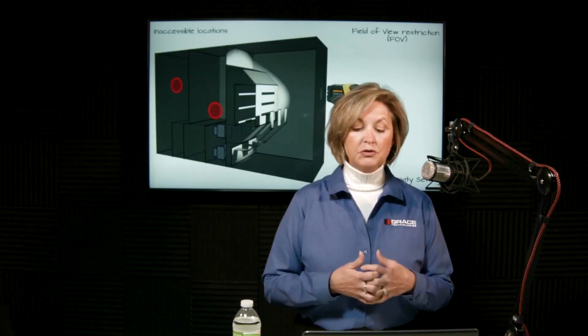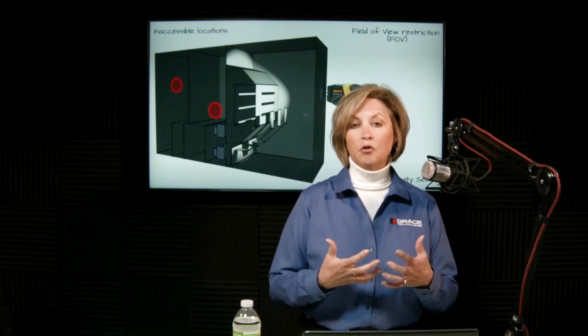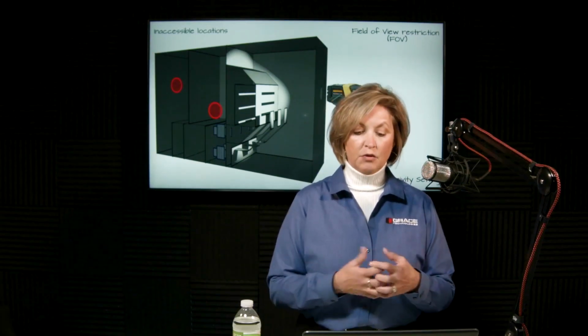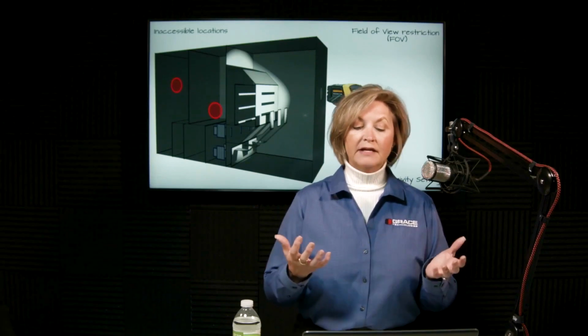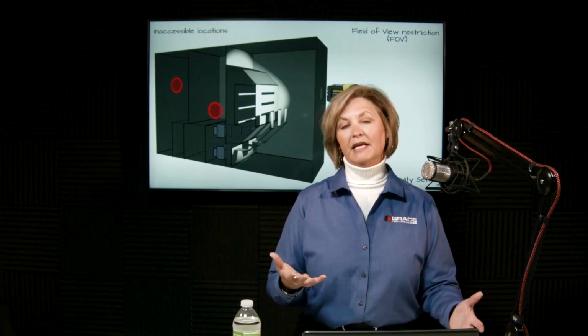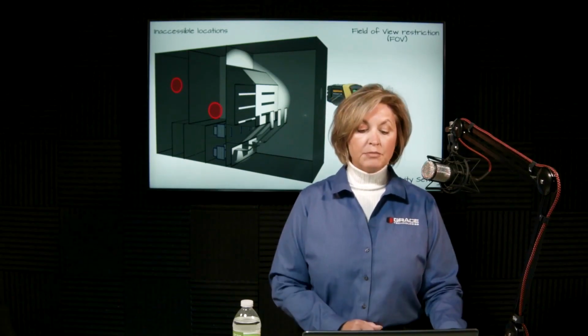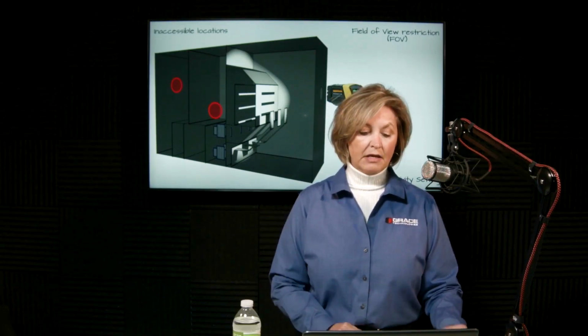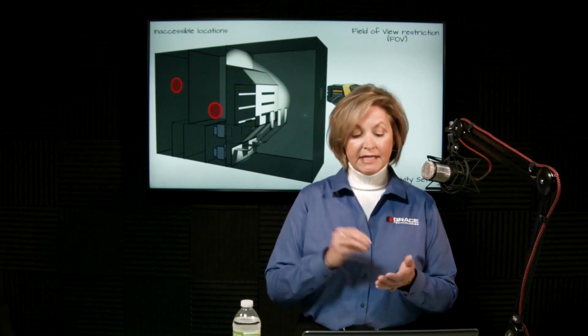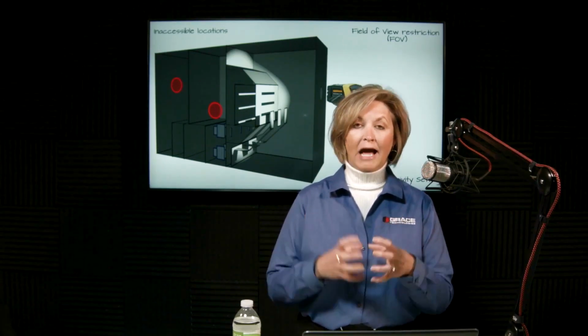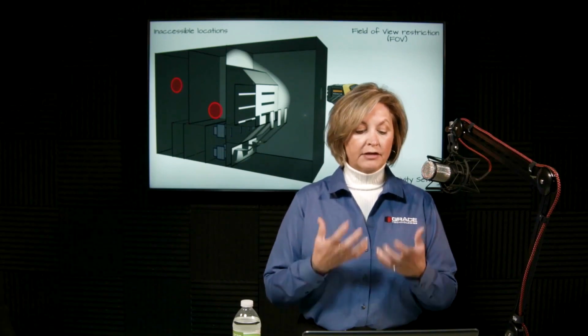Thermal scans through windows do provide a partial solution to the problem by allowing the camera to capture thermal data within energized equipment. However, complete line of sight to all the critical locations can't always be achieved because there are often cables or safety barriers obstructing the view of these connections. So installing a thermal monitoring or continuous monitoring solution will not only capture the thermal data on energized equipment, but also reach those critical points well beyond what would be visible through a window.